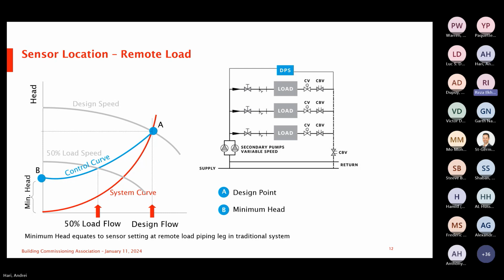But that's something that we need to check during the commissioning of the project when the balancer is coming, to give us that number for the DPS set point, to look at all different zones and risers and make sure that at any certain set point, everywhere is getting enough flow. That's my question one. And question two, that scenario can happen in any other location, not necessarily closest to the mechanical, right? Yes, you're absolutely right. It can happen in any other location.